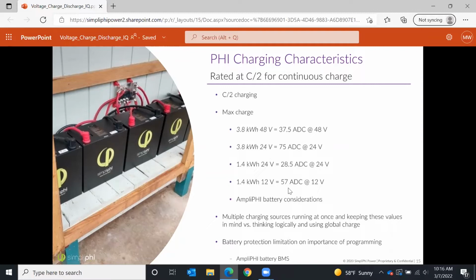Here are the respective charge and discharge rates of the other batteries as well. And some considerations when you're looking at this same thing with SimpliPhi: remember that the SimpliPhi has the same charge and discharge characteristics, but it can limit its own charge and discharge by communicating. So you don't necessarily need to size your battery bank to fully power your inverter if you're using SimpliPhi.